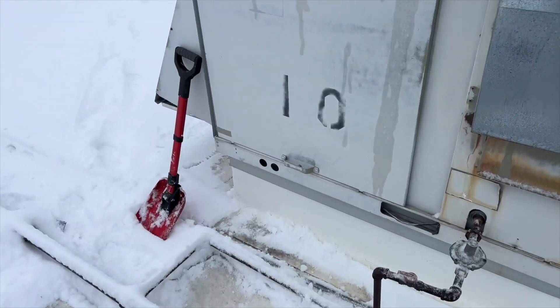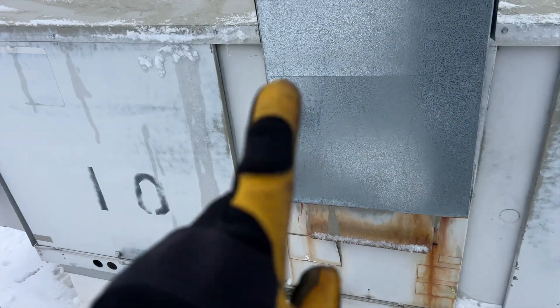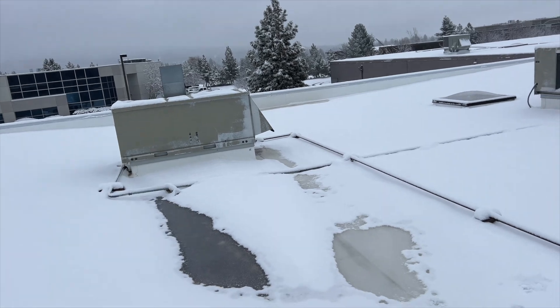We're back on the roof. We got two units that are down. This one's not heating — the inducer's running, but I don't feel any heat. And that one over there is number 11, so that one's also not working. I haven't looked at that one yet.